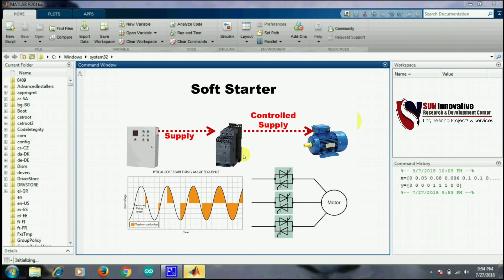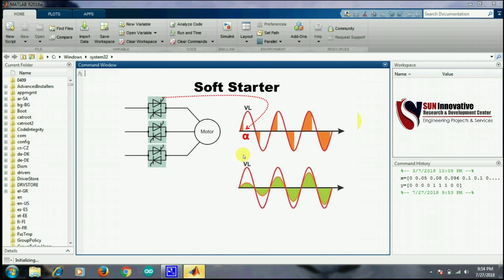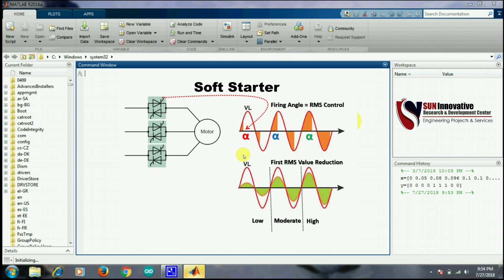As you can see in the diagram, thyristors are used in a soft starter and the input voltage can be controlled by the firing angle alpha. At the initial time, due to inrush current, the firing angle must be set to high values because we need to reduce the RMS voltage for the first few cycles. After the inrush current settles and the inductor windings are charged over the previous two or three cycles, we reduce the firing angle to increase the RMS voltage, thereby controlling the inrush current.